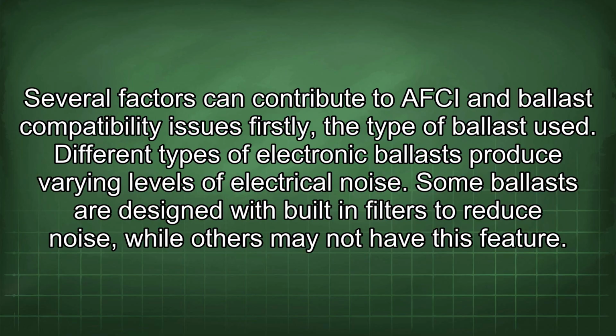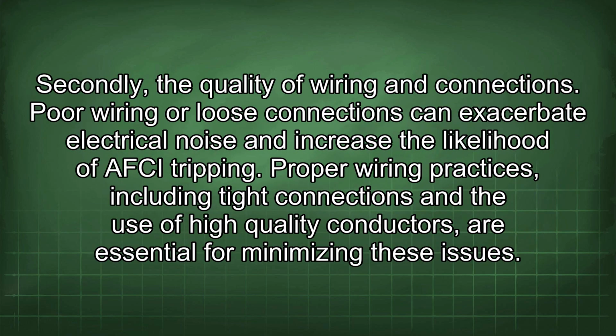Firstly, the type of ballast used. Different types of electronic ballasts produce varying levels of electrical noise. Some ballasts are designed with built-in filters to reduce noise, while others may not have this feature. Secondly, the quality of wiring and connections. Poor wiring or loose connections can exacerbate electrical noise and increase the likelihood of AFCI tripping. Proper wiring practices, including tight connections and the use of high-quality conductors, are essential for minimizing these issues.